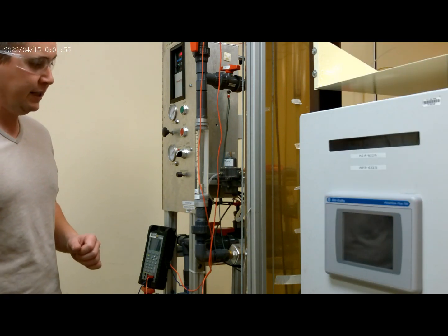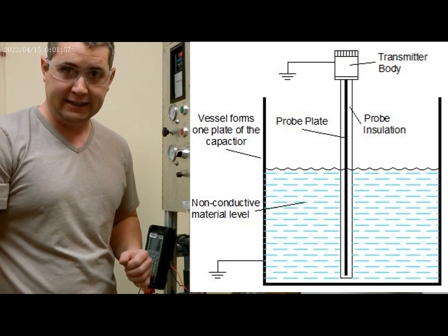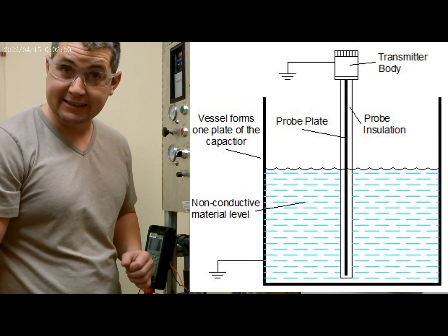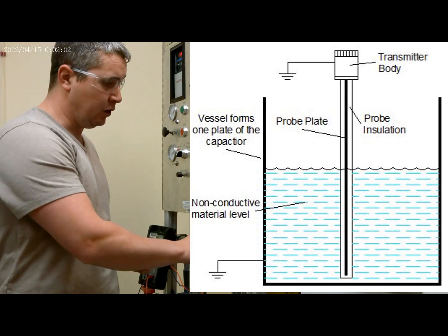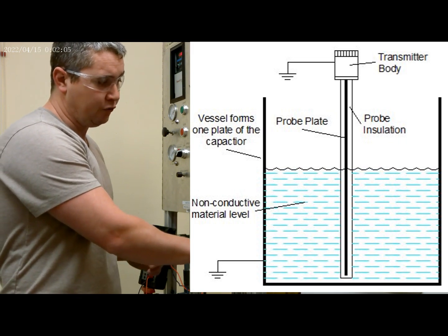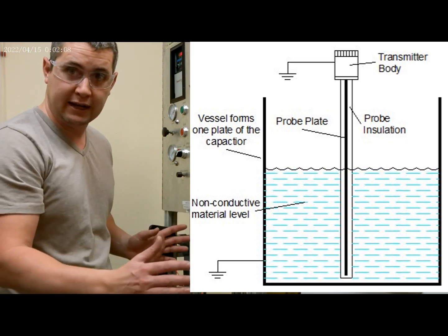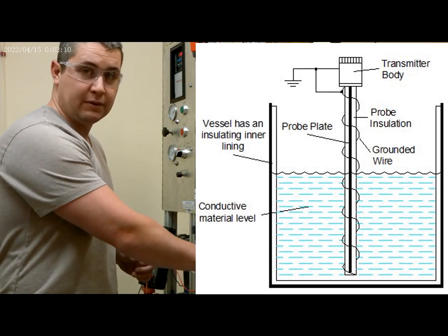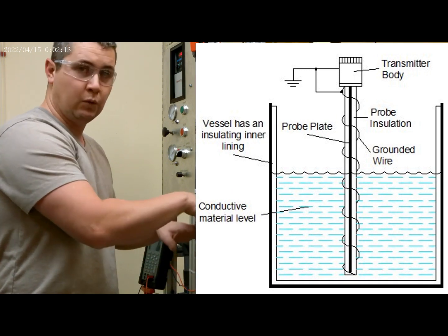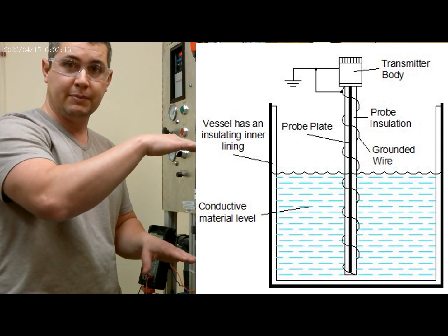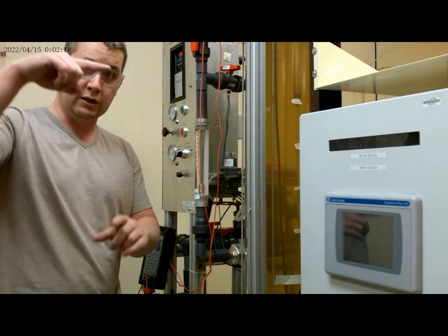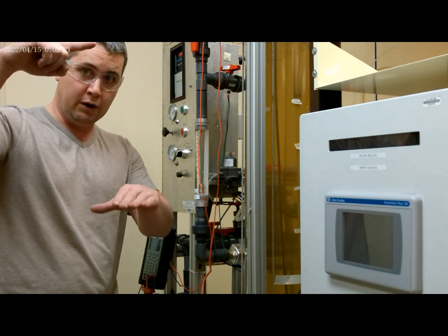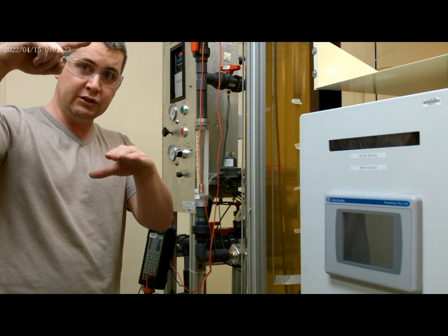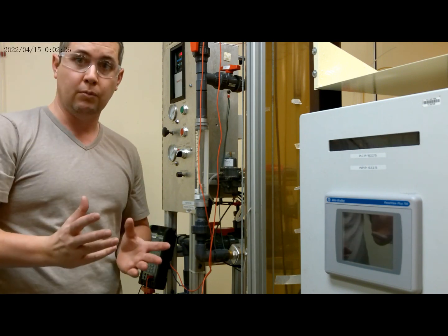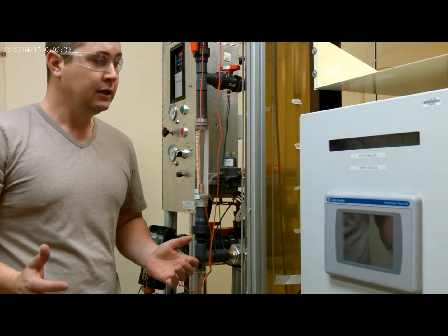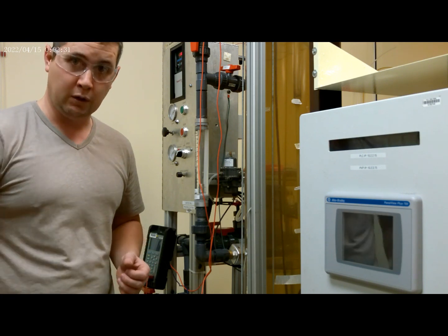We know that the capacitance probe works off capacitance. It works on the fact that it can go from the capacitance probe to the outer wall of the tank, or from the bottom of the probe up to wherever the water level reaches on it. A capacitance probe is a certain length of probe, and as the water level increases on it, it changes the dielectric material around the probe, which changes the capacitance. Based on the capacitance, we can tell the water level.